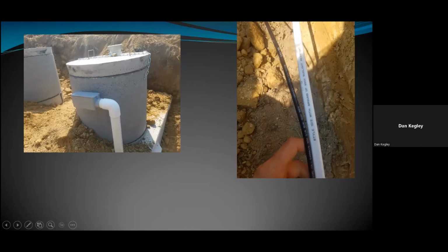On the right-hand side, you notice the UF wire. It does say 12-2 with ground UF, so underground feeder wire style. They come in all kinds of different colors. You will see gray, kind of a dark gray. UF cable is more commonly that color, but they do have white. I've seen yellow. I have seen orange UF wire, which is kind of confusing with the indoor wire, but they do make different colors. You can especially ask them to make it.